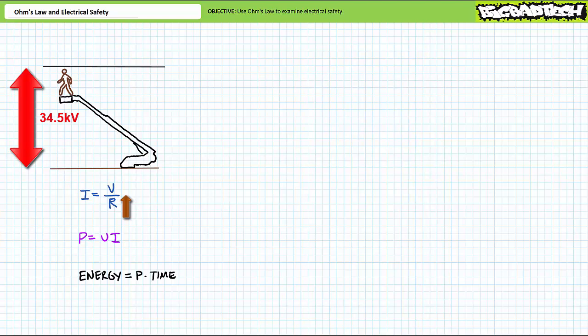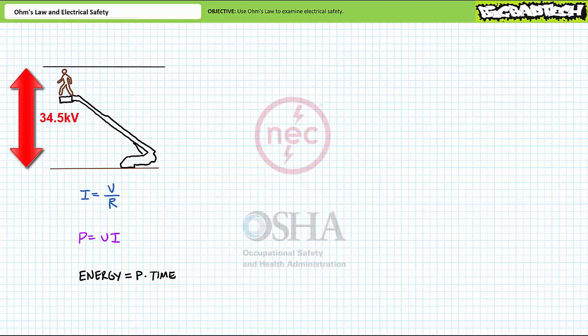Step three, if all else fails, don't get shocked for long. If energy is power times time, the longer you are a conductive path, the more energy will be transferred to you. It is for this reason systems often incorporate protective mechanisms such as fuses and ground fault current interrupters to limit the length of high current or fault current events. We'll examine these devices in later lectures.